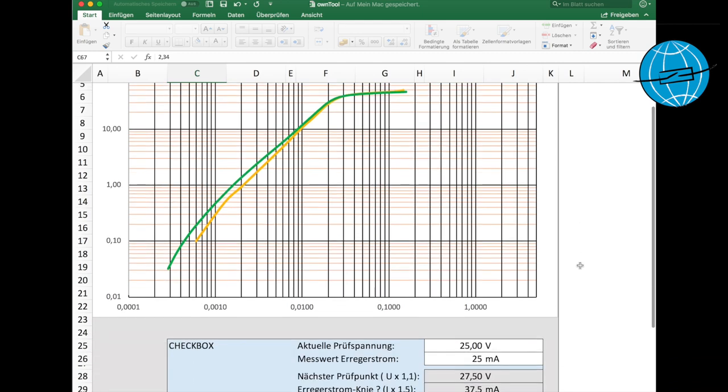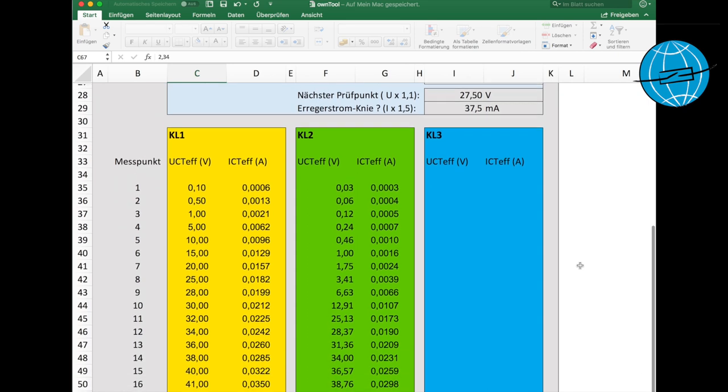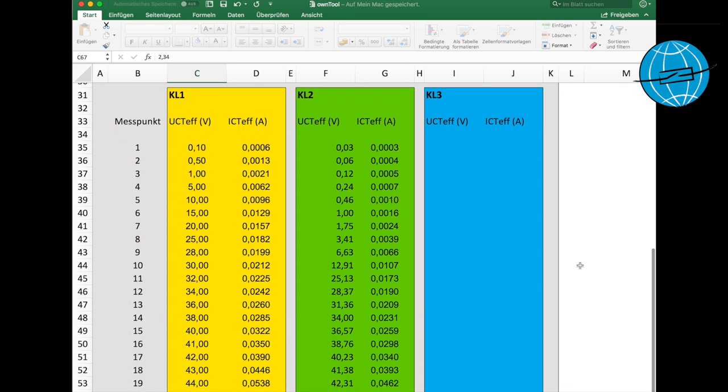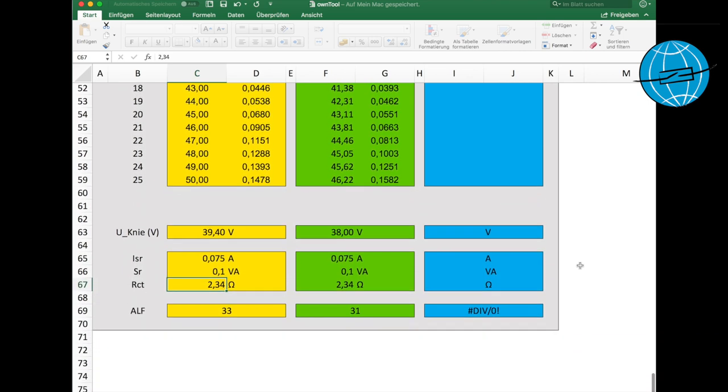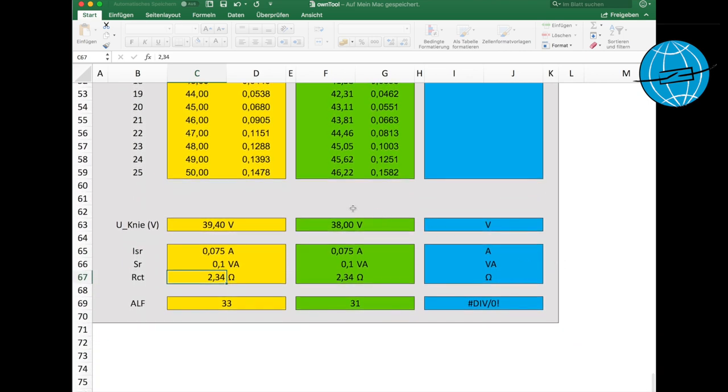You can enter up to three curves in this Excel tool which can be either three cores or three phases. And at the bottom you can get the accuracy limit factor ALF calculated. Simply enter the knee point voltage, the secondary rated current, the rated power of the core and the winding resistance of the core to obtain the result. I've done this in advance as well and our ALF is about 30 at a rated power of 0.1.